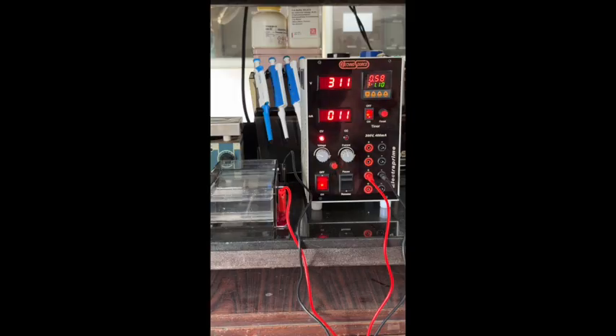Cannot set current to desired value. This happens when there are high voltage values exceeding the limit that is set or the capacity of the power supply, due to which the power supply has switched to the CV mode. This can be confirmed by checking if the LED indicator for CV is lit up.